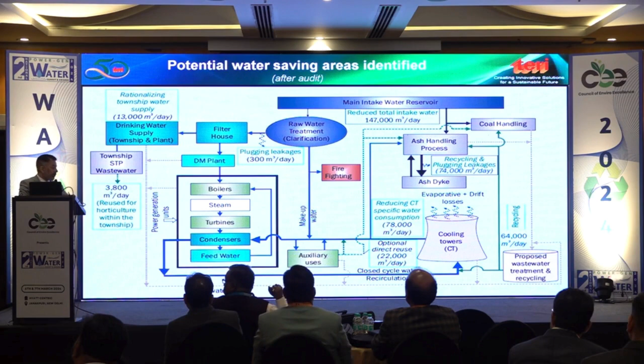If you look at the ash handling system, recirculation savings of around 50 to 80% were possible - the loss into the ash handling system could be saved by increasing recirculation of water, plugging leakage losses, and increasing the cycle of concentration. Cycle of concentration is basically the closed cycle between the cooling system and the condenser system - the more times you can use this water, the better the efficiency, because you don't need fresh water for makeup.